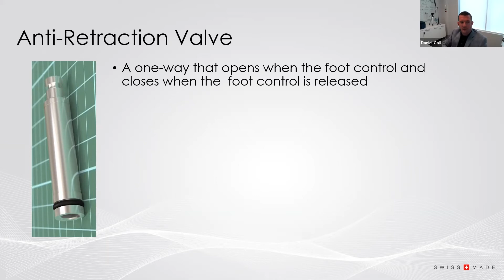The critical thing, and this is something BNR has always strived to meet, is the highest standards of infection control. We're a principles-first company, and we want our products to follow the most advanced standards of infection control, regardless of where the recommendations are at. Most of the handpieces on the market with fixed back ends do not have an anti-retraction valve at all. Most of the handpieces that have couplings do have anti-retraction valves, and the valve is located in that coupling. That coupling is not removed from the handpiece tubing between patients and not sterilized.